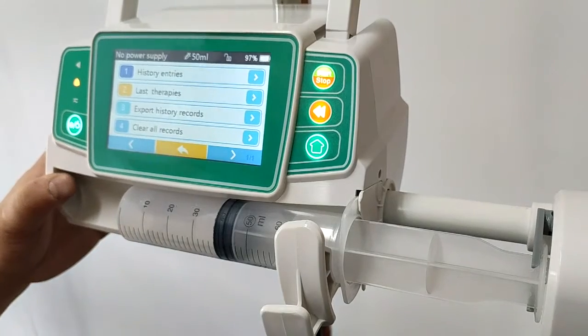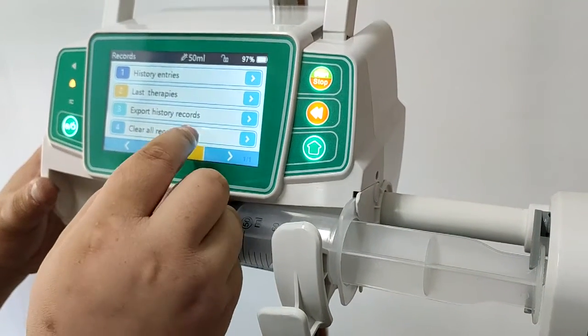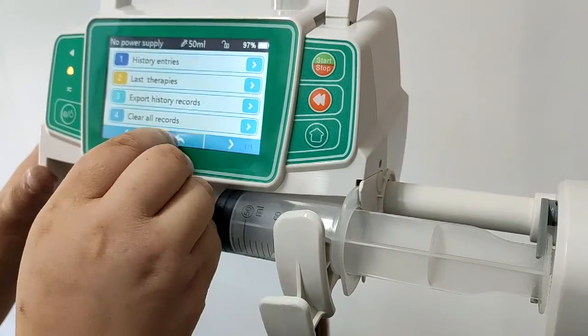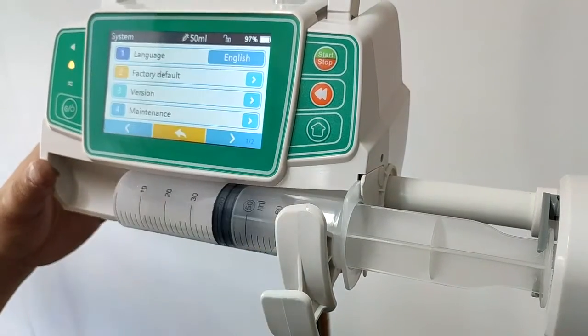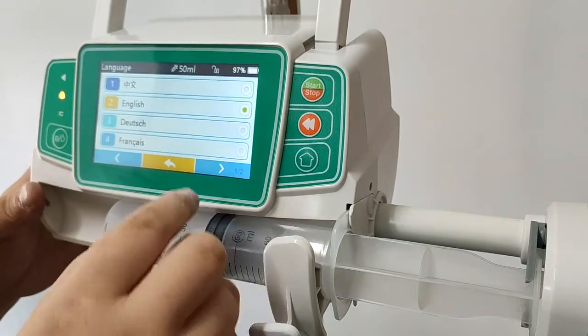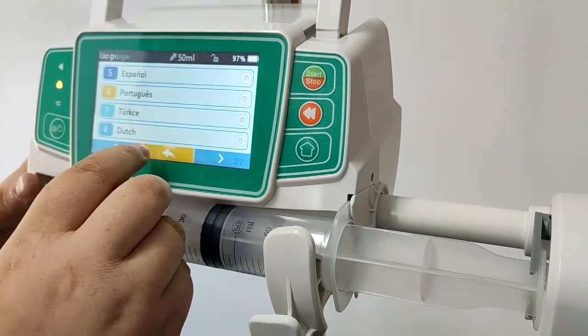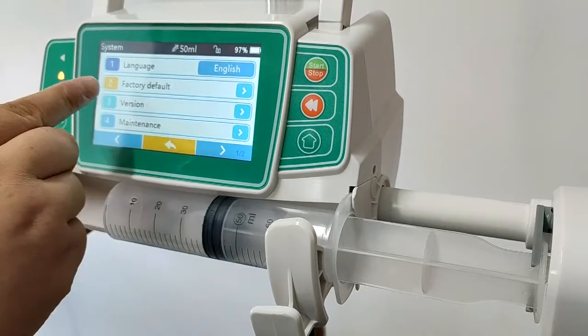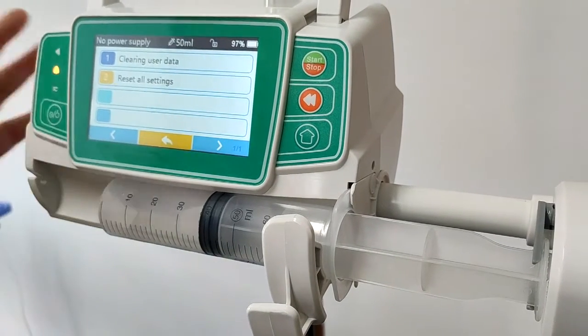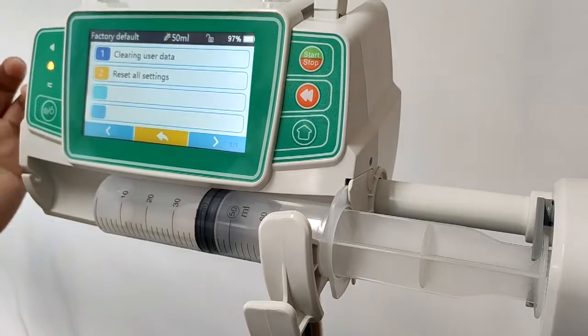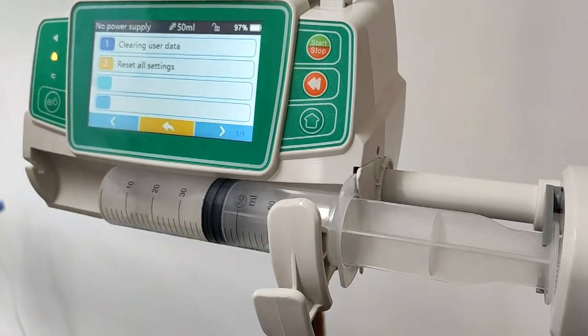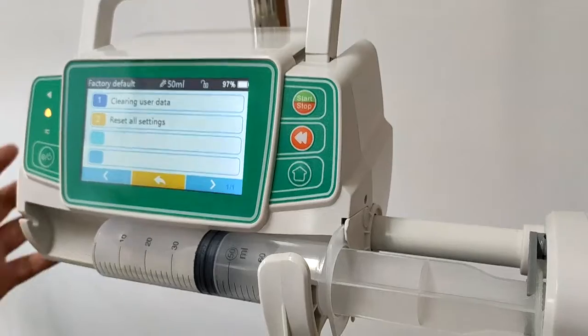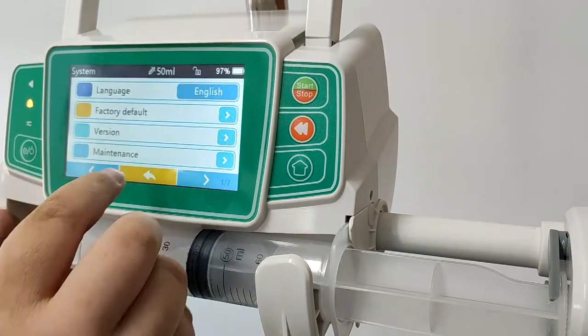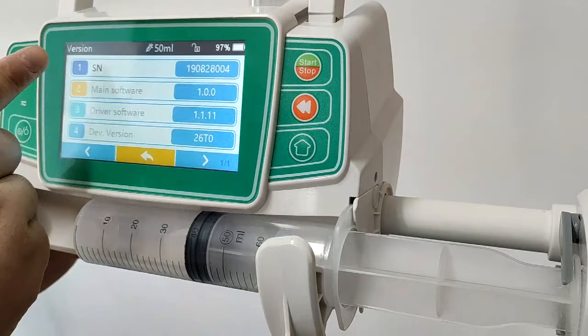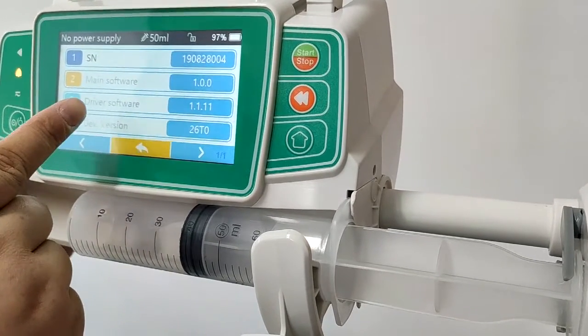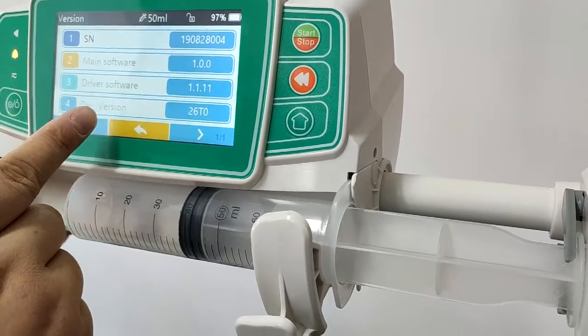And you can also export history records and clear all records with the password. And by the system interface, you can change the language of the pump. Now we have different languages. And by the factory default, you can clear user data or clear all settings if you don't know whether you have set some parameters by mistake, but you will require the password. By the version, you will find the serial number and the main software version and the driver software as well as device version.